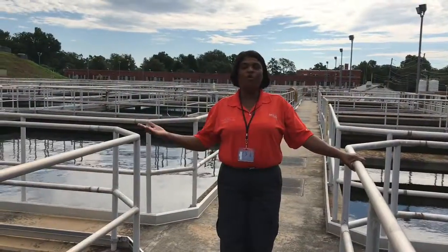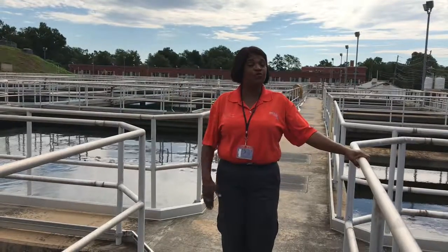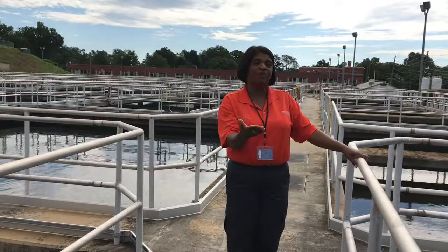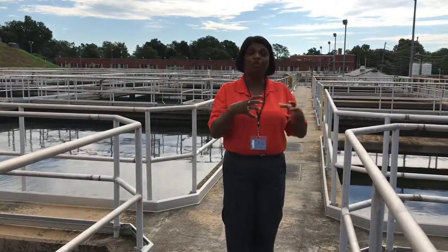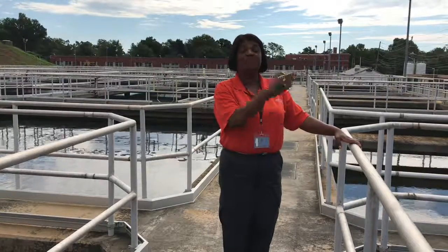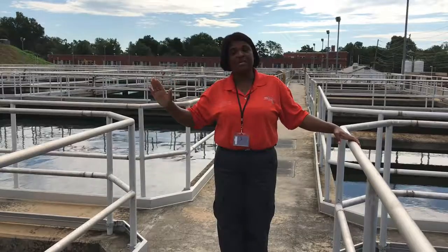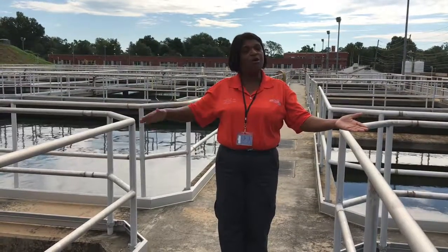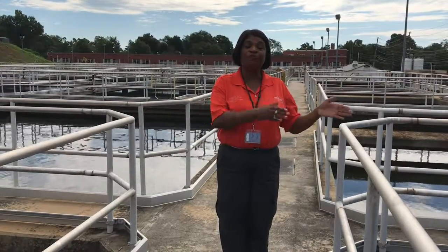Hello, we're out in front of my water basins, and this is what I was talking to you earlier about, the raw water that's coming from the reservoir. Here we have coagulation. This is when we add positive chemicals to negatively charged things like sand and silt in the water. They join together like a magnet. And then we have flocculation, which we have flocculators that spin and make the particles larger, and they settle out. So therefore we have sedimentation as well. So we have coagulation here, flocculation, and sedimentation. And the whole process is anywhere from 2 to 4 hours.